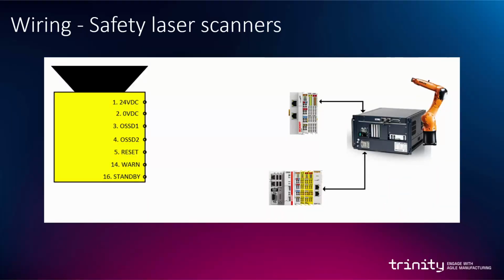We will now take a look at how the previously seen connections should be connected into a robotic system. On the left you see the laser scanner and the wiring terminals that we've chosen and the labels that they represent. And on the right we have a KUKA KRC4 robot controller that has been connected into a basic input-output terminal and a safety input-output terminal. As a main power source for the safety scanner, we will use a 24-volt output from the basic input-output terminal.